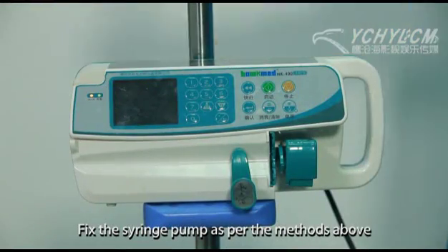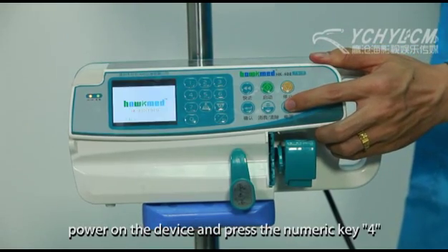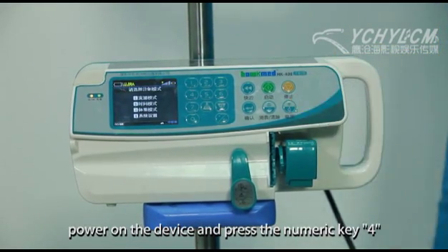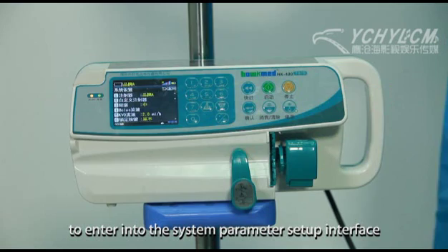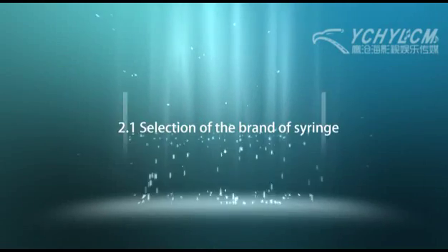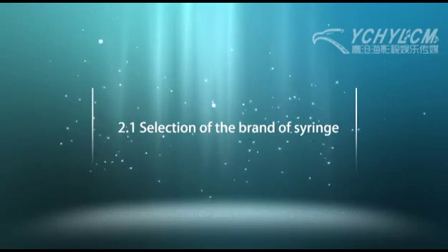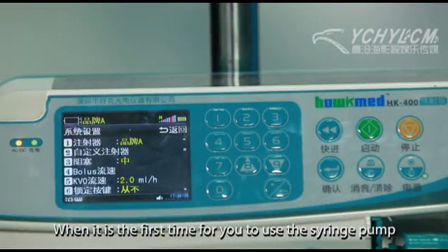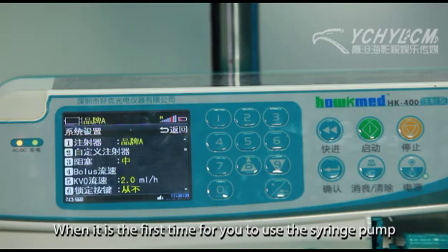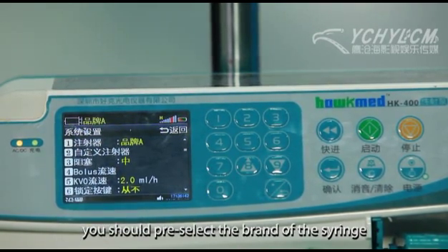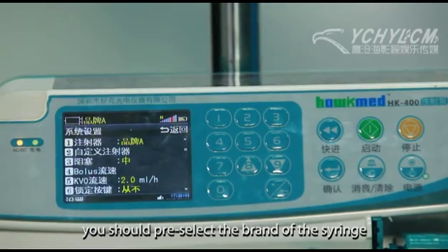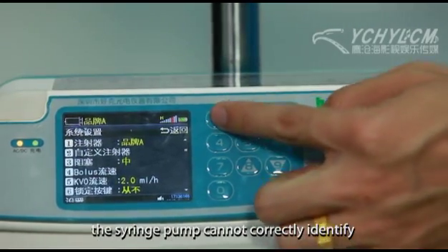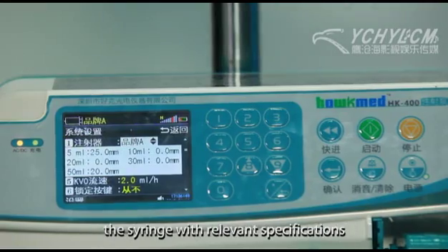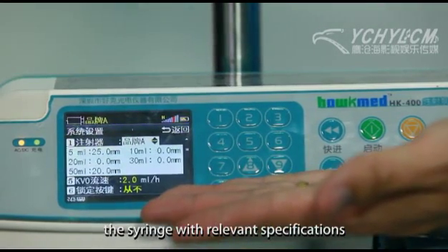Fix the syringe pump as per the methods above. Power on the device and press the numeric key 4 to enter into the system parameter setup interface. Selection of the brand of syringe. When it is the first time for you to use the syringe pump, you should pre-select the brand of the syringe. Otherwise, the syringe pump cannot correctly identify the syringe with relevant specifications.